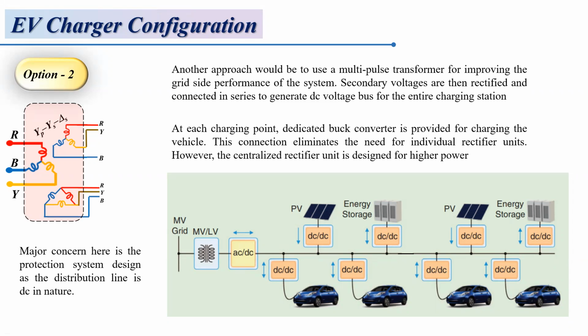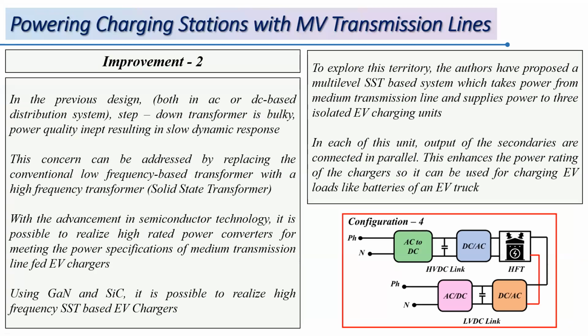As you can see, in both these options the major problem is the low frequency transformer. With advancements in semiconductor technology, it is possible to replace that low frequency transformer with a high frequency transformer, termed a solid state transformer.